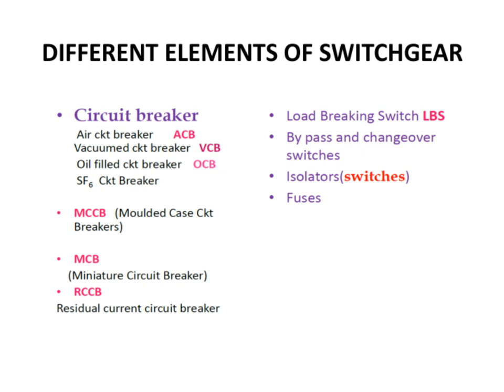These elements are vital for ensuring safety and reliability in power distribution. First, we have the circuit breaker, which is designed to automatically disconnect a circuit in case of overload or short circuit. It acts as a safeguard to prevent damage to the system and ensure safety. Next, there are disconnect switches, or isolators, which allow us to manually open or close circuits for maintenance or safety reasons. They provide a visible break in the circuit, making it clear that the section is de-energized.